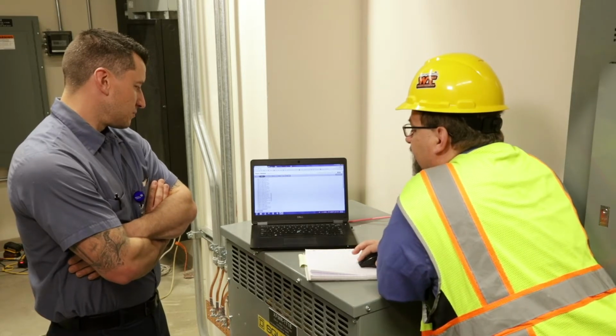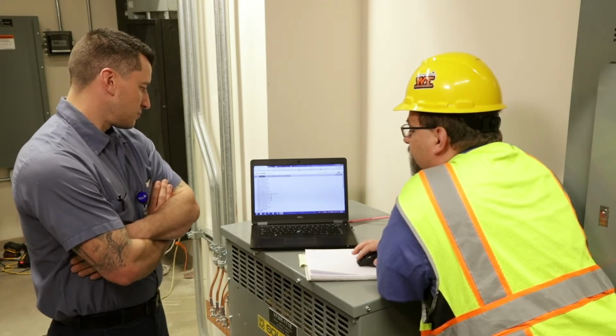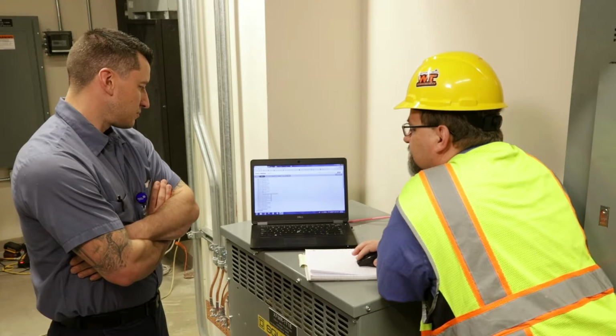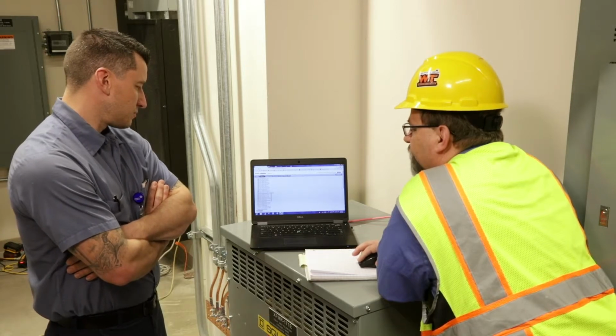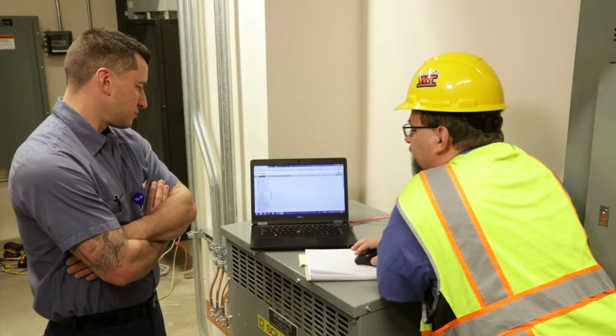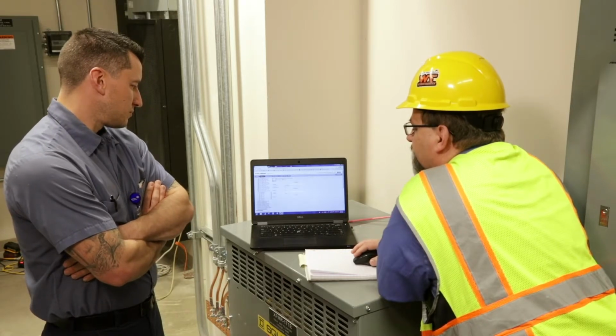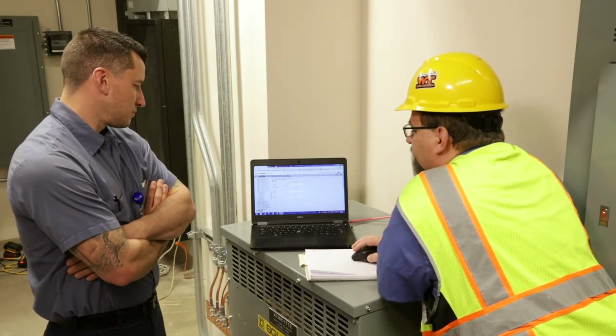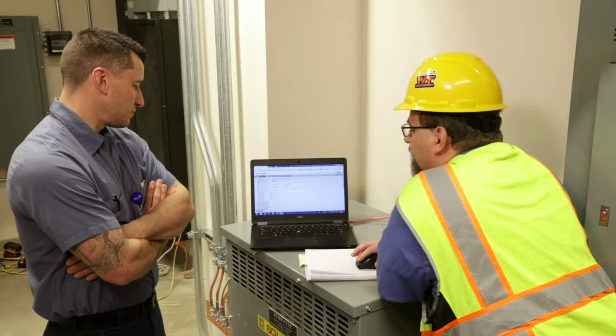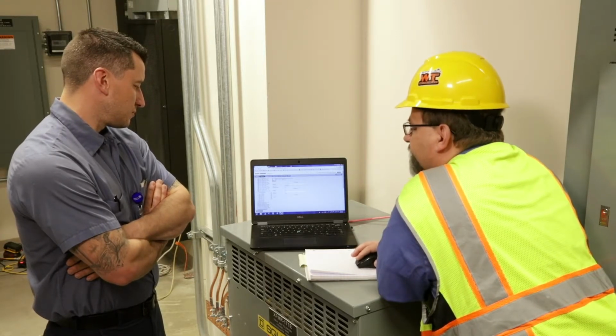So if you click into that, first of all, this is online. This is talking to us because it's not yellowed out. If it was yellowed out, it would be offline. I can see the sensors. I can see the room controller at the top here. I can see what the settings are and things like that. I can come down to the load, right? So it's kind of a hierarchy, and you drill down from the different areas.